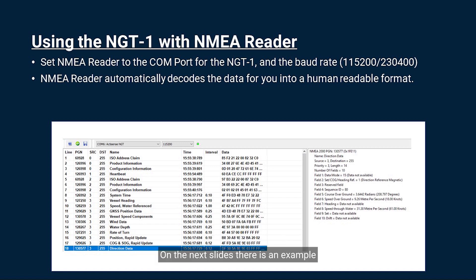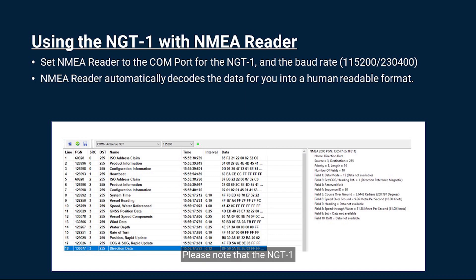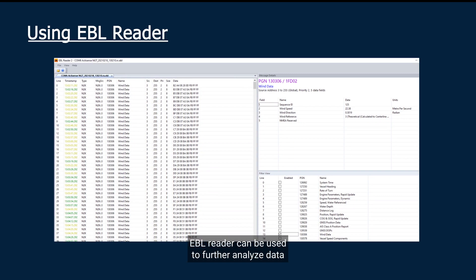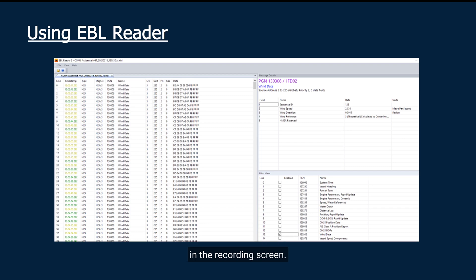On the next slides there is an example of an EBL recording being analyzed using ActiSense EBL Reader, and how it can be exported into a CSV file. Please note that the NGT1 can receive proprietary messages from other manufacturers, but we cannot decode them. EBL Reader can be used to further analyze data and filter that data so that you can see exactly what you want without the other data being in the recording screen. This makes problem solving much easier.